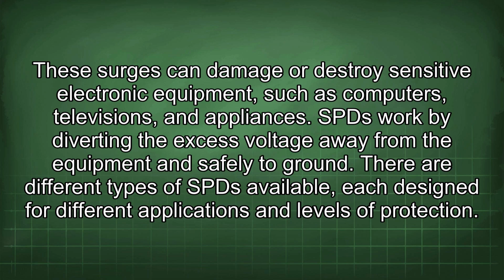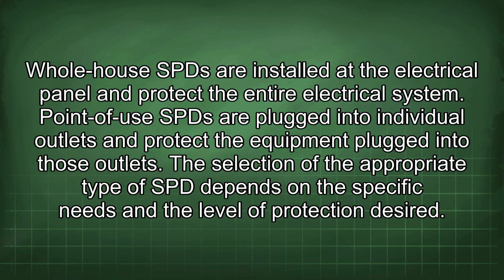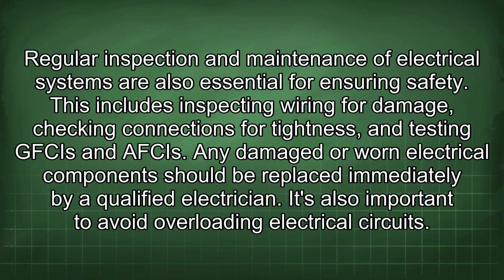There are different types of SPDs available, each designed for different applications and levels of protection. Whole house SPDs are installed at the electrical panel and protect the entire electrical system. Point of use SPDs are plugged into individual outlets and protect the equipment plugged into those outlets. The selection of the appropriate type of SPD depends on the specific needs and the level of protection desired. Regular inspection and maintenance of electrical systems are also essential for ensuring safety. This includes inspecting wiring for damage, checking connections for tightness, and testing GFCIs and AFCIs. Any damaged or worn electrical components should be replaced immediately by a qualified electrician.